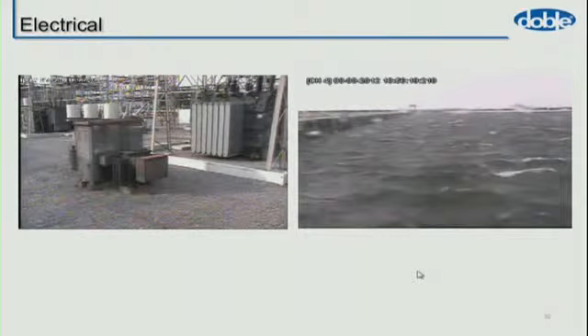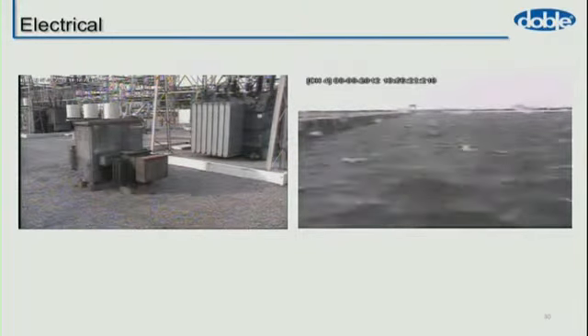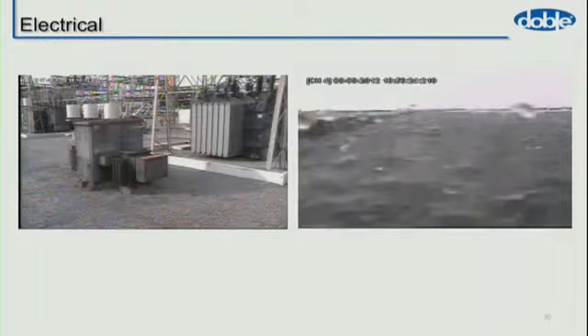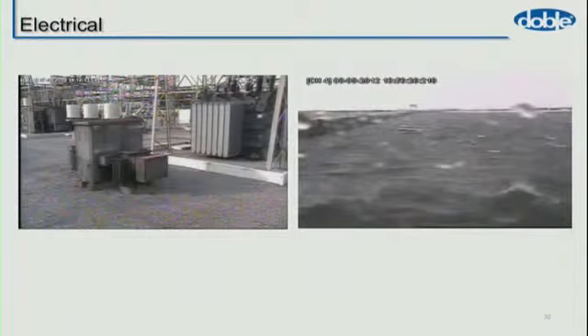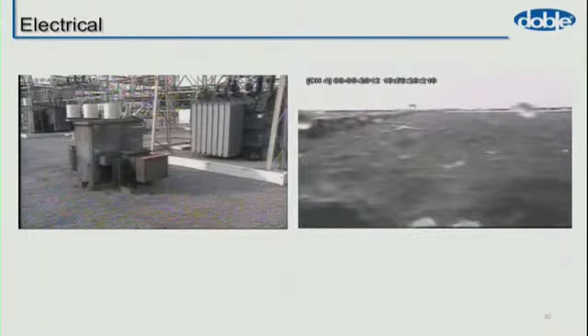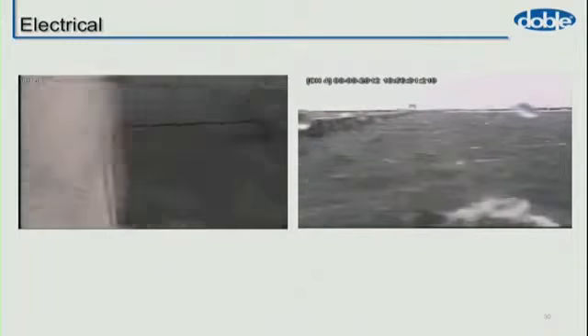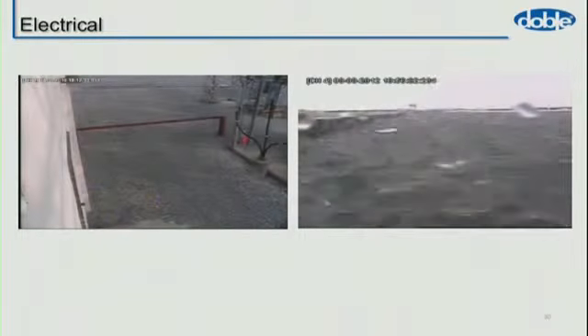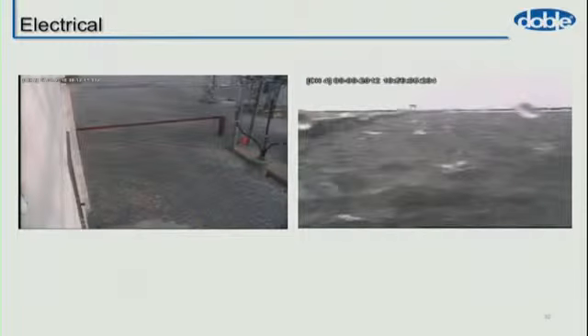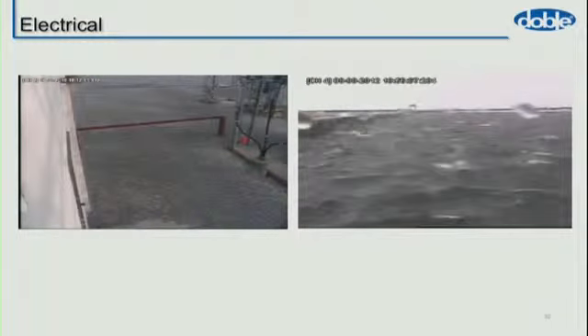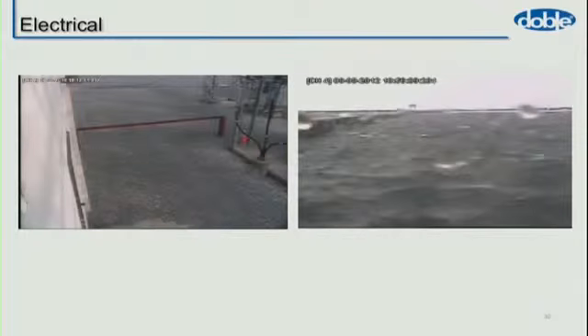So the video on the left is very, very quick when it happens. That's a bushing failure. How much monitoring would you need on this substation on the left to be able to detect a bushing fail? You could sit there for 50 years seeing nothing. There has to be a cost benefit to justify that failure being identified.